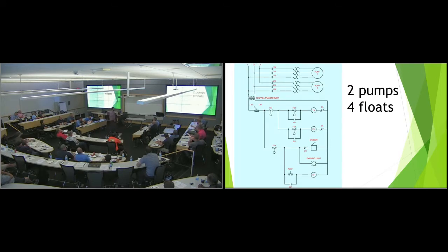What are we looking at here? This is ladder logic. We have two pumps, a control transformer, a two-position selector switch, multiple floats, a buzzer, and a control relay. Right now this might look like nothing to you, but by the end of this you're going to understand it. We have three-phase at the very top connected to two motors, a control transformer that steps down the voltage, and then all of our controls down below.